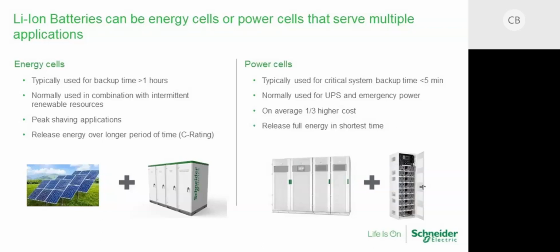On the contrary, the energy cell is capable of providing longer backup times. We see 1 hour, 2 hours, 4 hours, depending on how the system is configured. As a result, it can release its stored energy over a longer period of time, not as fast as the power cell. That's what's called the C rating, and we will see this in a little bit. Typically, battery energy storage systems with energy cells are used for peak shaving applications. They're also normally used in combination with intermittent renewable resources, specifically wind and solar, because the wind's not always blowing or it's changing.